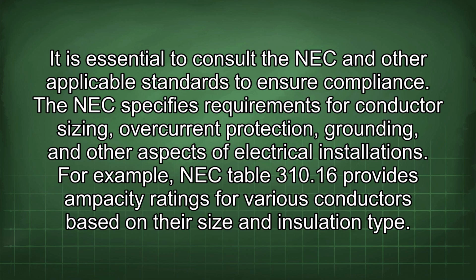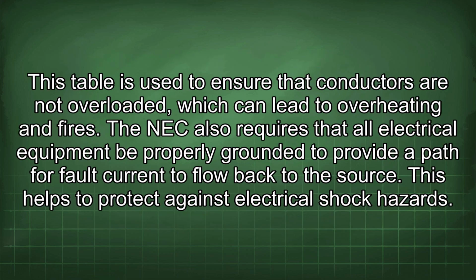The NEC specifies requirements for conductor sizing, overcurrent protection, grounding, and other aspects of electrical installations. For example, NEC Table 310.16 provides ampacity ratings for various conductors based on their size and insulation type. This table is used to ensure that conductors are not overloaded, which can lead to overheating and fires. The NEC also requires that all electrical equipment be properly grounded to provide a path for fault current to flow back to the source. This helps to protect against electrical shock hazards.